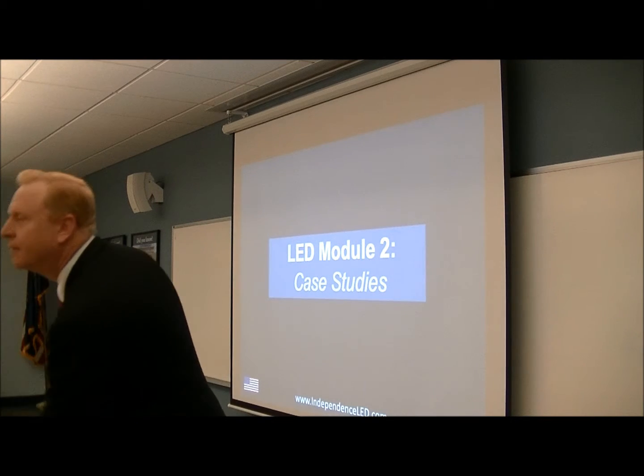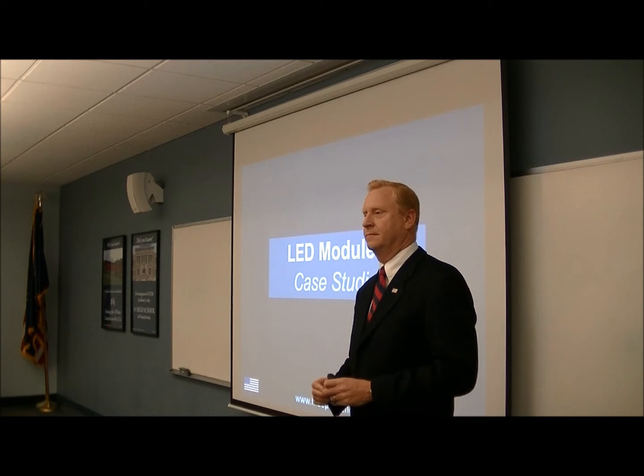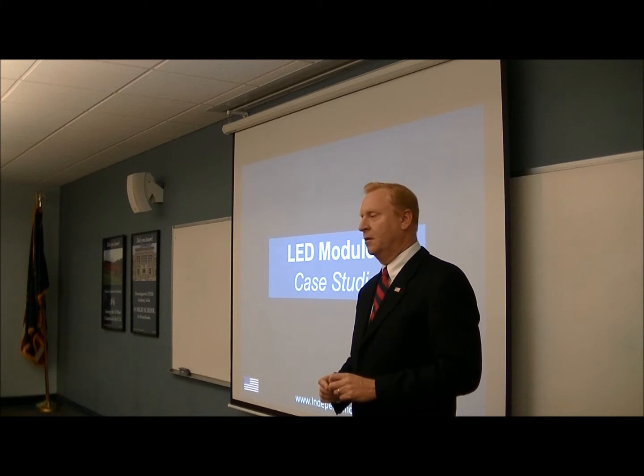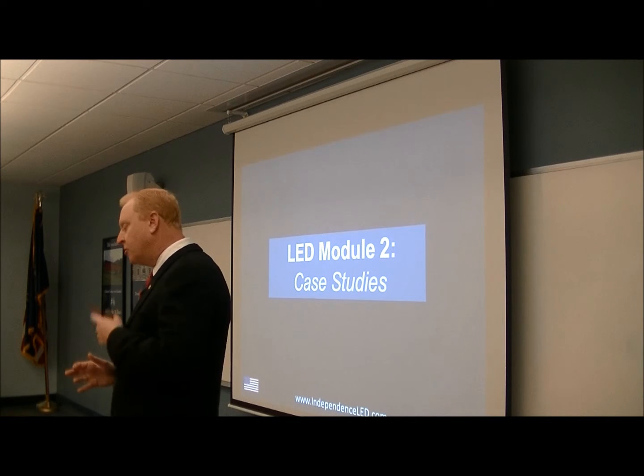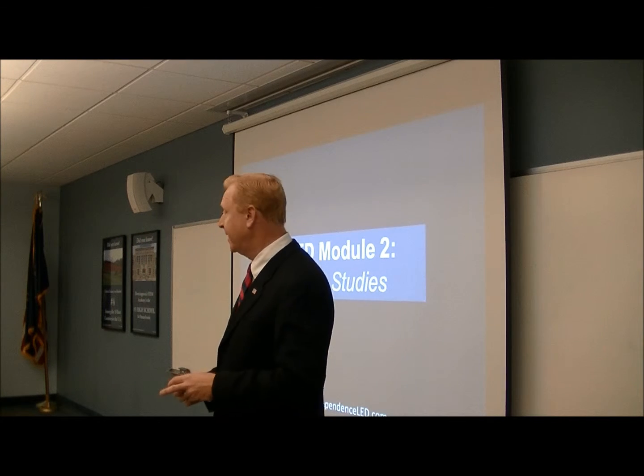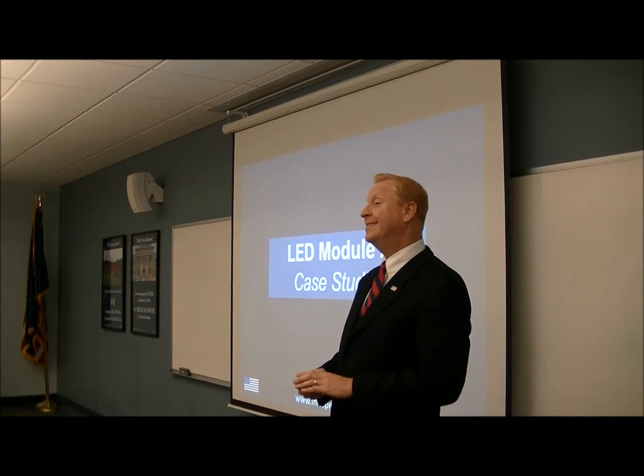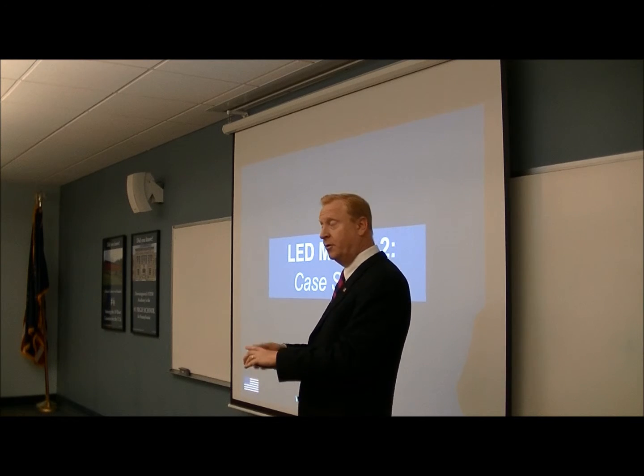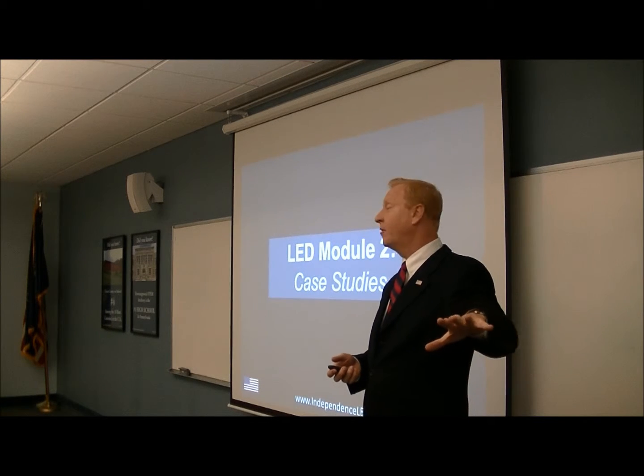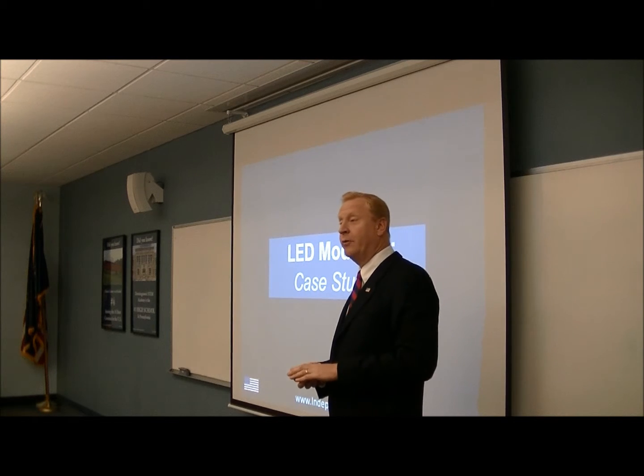One of the other questions, one of the aesthetic issues I have with it is when I try to use an LED, it's the Kelvin rating that becomes a problem. So has anything changed with the Kelvin rating on LEDs? So the most common Kelvin in commercial applications is 4100. That is sort of a neutral white. The bluer white bright light is in the 5000 and 5500 range for parking, hospitals, industrial. And then the residential and warmer for hospitality is often in the 2700 to 3500 range.